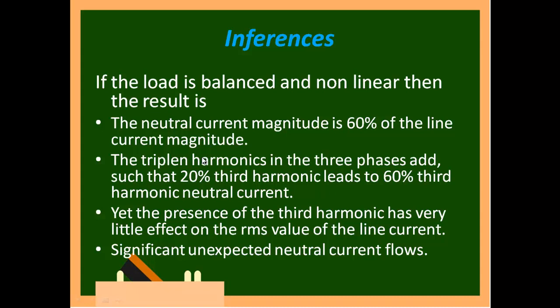So always the issue created by third harmonics is worst compared to all other harmonics. Yet the presence of third harmonic has very little effect on the RMS value of the line current. Even yesterday we have seen third harmonics is going to increase RMS only a little, but you can see how much it is affecting your neutral current.